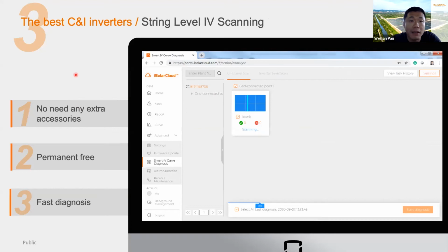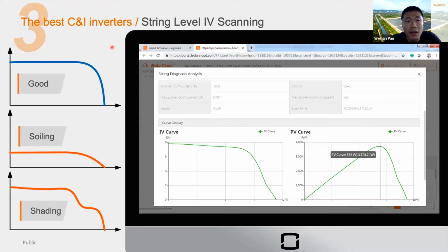And the third one is iSolarCloud and the IV curve scanning, with permanent free use. I want to emphasize it's totally free for as long as you install our inverter, and without any extra accessory required. You could simply use our iSolarCloud to conduct a fast diagnosis of the PV string. But what is the concept behind the IV curve scanning? In our iSolarCloud, we built in several algorithms. For example, this one is a good condition IV curve, and then we have a database built in. If the PV panel is covered with dust or dirt, it will look like this. And for the partial shading condition, the IV curve will look like stairs.